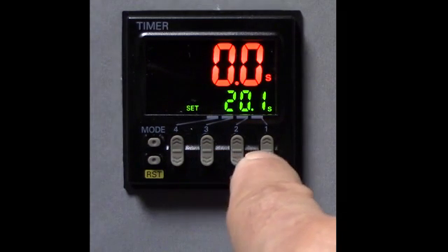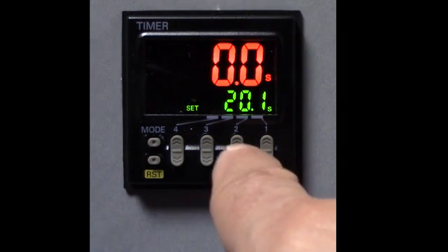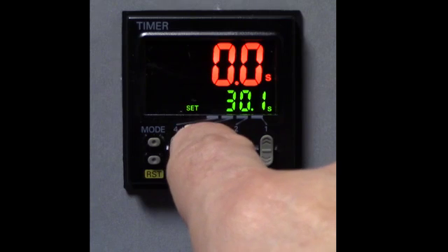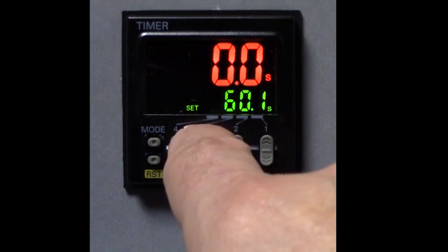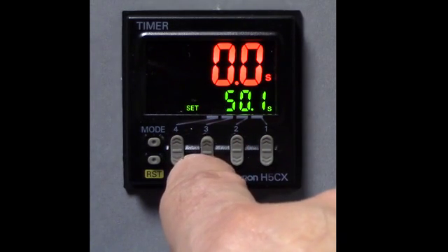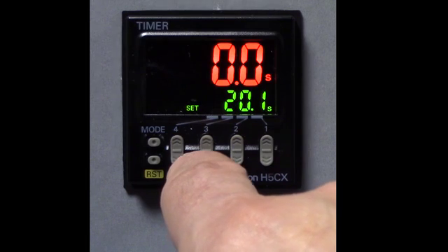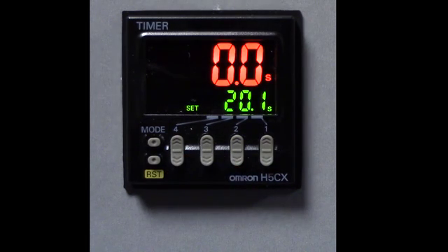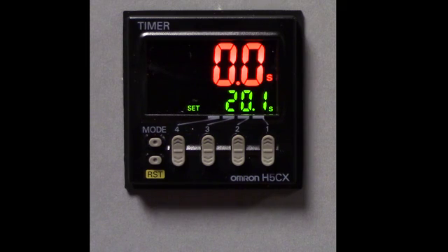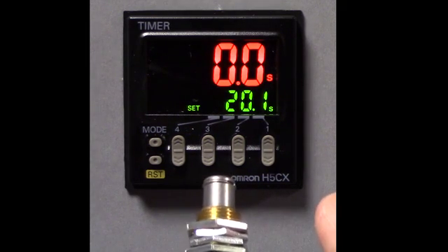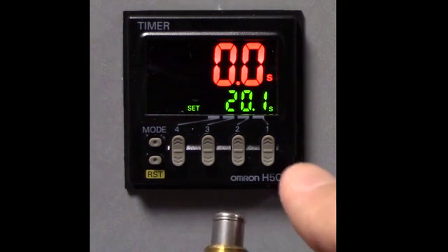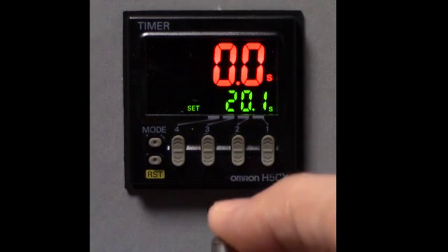As you notice, I've been hitting the bottom of the key. If you hit the top of the key, that'll allow you to advance in your numbering. If you hit the bottom of the key, that allows you to go backwards. So you don't have to cycle through the whole number. So that being the case, we have it set for 20.1 seconds. And I am going to press our basic switch, our snap action switch, and begin the timing process.